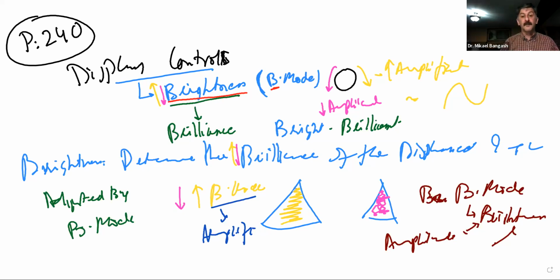Where we said there were two ways to reduce the brightness of the image. In context of ALARA, we said if your image is too bright, the ideal thing to do would be to reduce the power output. Whereas just reducing your B mode, by turning it anti-clockwise, is going to cause the signal to be amplified to a lesser extent. That reflection may be amplified to an amplitude like this, which may be just right.